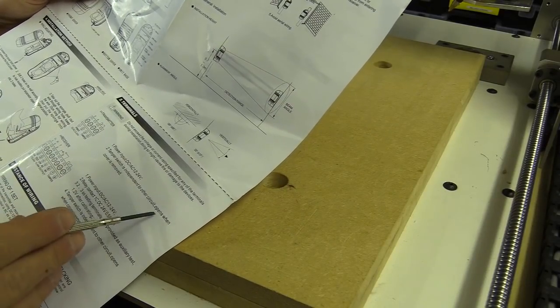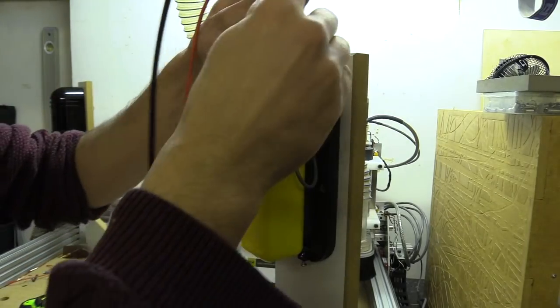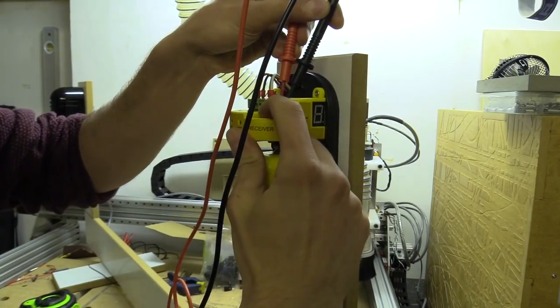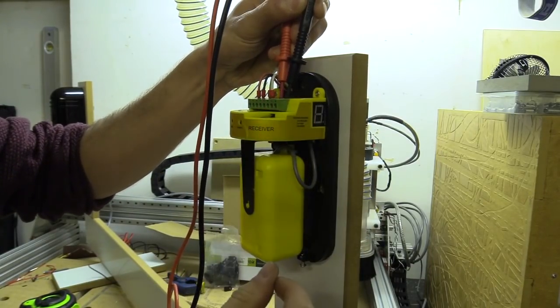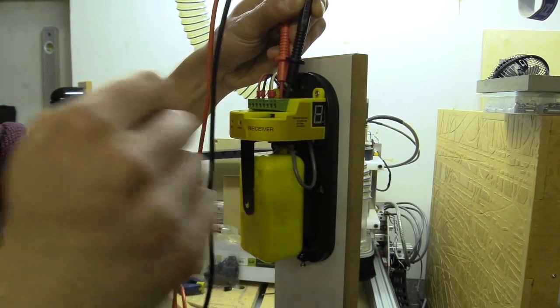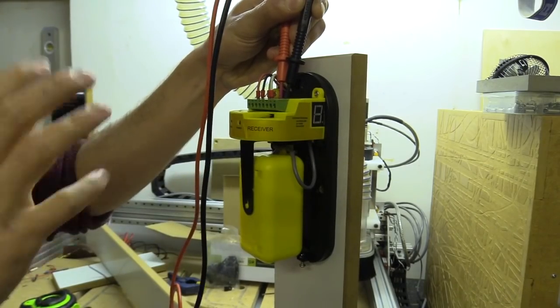I'm now going to show you what the tamper terminals are doing with a voltmeter. When the cover is on the terminal produces a closed circuit and when removed the connection is broken. So when the cover is on this is seen as a normally closed connection and when that comes off it will then go to normally open.